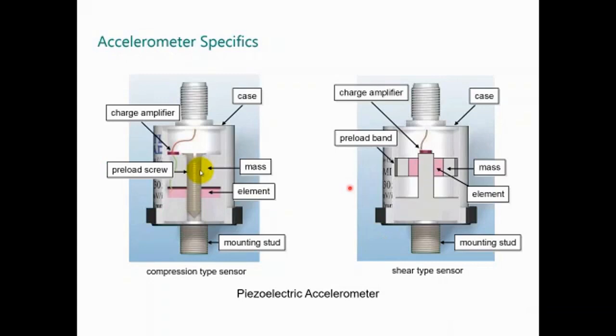There are two different designs. The old design is the compression type, and the new design is the shear type. In both cases, we have a mass. In the previous design, using a preload screw. This is the element - the piezoelectric crystal. And this is the case, with the charge amplifier. Here the element is around this shaft, and this is the mass, and this is the preload band.